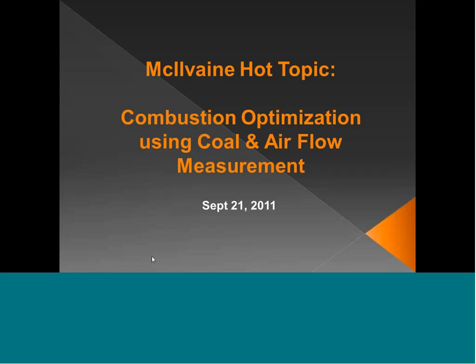Sure. Progress Energy, on the job that they presented, which was the last slides I ended with, spent about $3 million on total installation costs. So, basic rule of thumb costs: it costs about $9,000 to measure coal in each coal conduit. It costs $3,000 to $4,000 for a coal valve in each coal pipe. And then the airflow measurement costs roughly $7,000 to $8,000 for a low NOx burner, depending on which burner, to measure the air. The controllability usually is already in that burner.